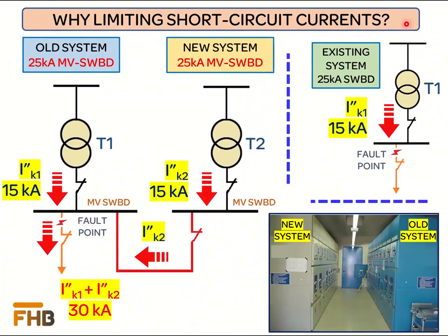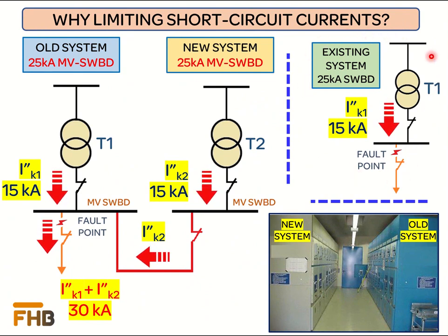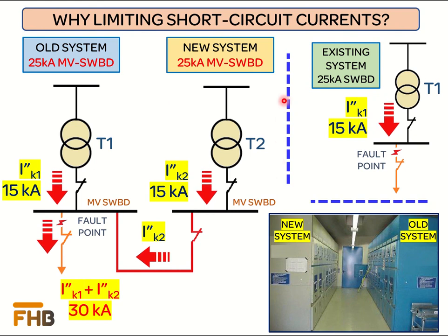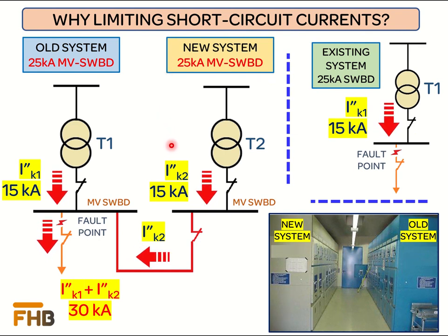To understand the need for current limiting devices, we consider a power network with an existing short circuit level of 15 kA. Considering this 15 kA value, the switchboard is designed at 25 kA, which is sufficient to handle short circuit faults. Now we expand our power network and add one more power line with a 15 kA short circuit value, and the switchboard is again rated at 25 kA. If the old and new systems work in isolation, there will be no problem as the short circuit values of the installed equipment match the isolated system values.